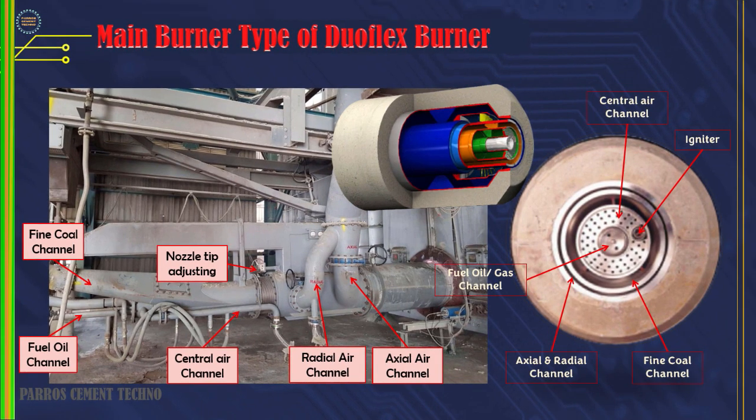This is a Duoflex burner. This type of burner's axial and radial air exits through a single channel, as shown in this burner nozzle image. For the operation of this burner, adjust the axial air valve opening 65 to 70% and the radial or swirl air 30 to 35%. The air pressure from the primary fan during normal operation is between 200 to 240 millibar.